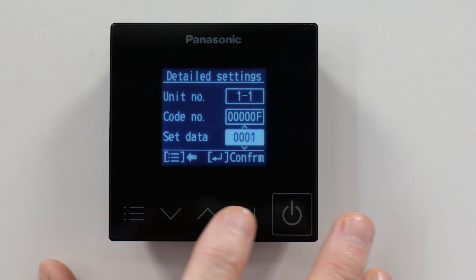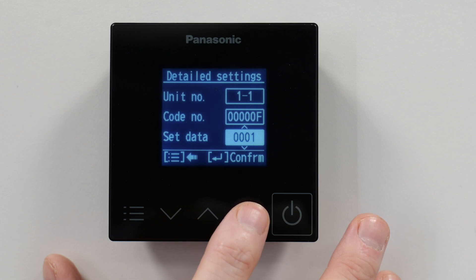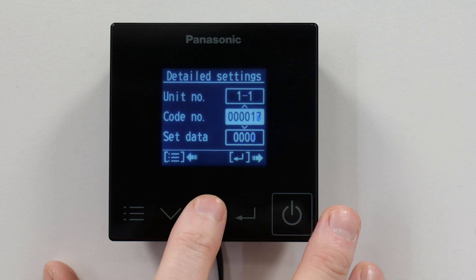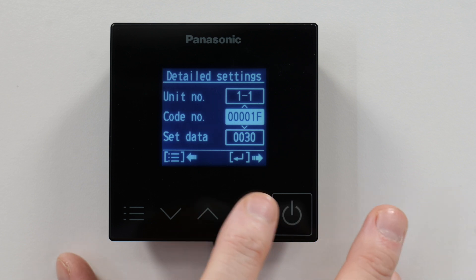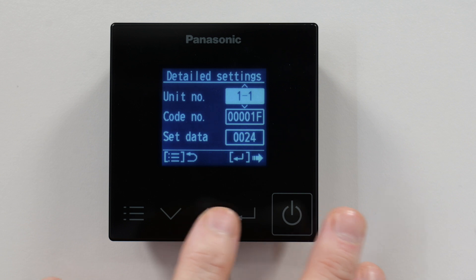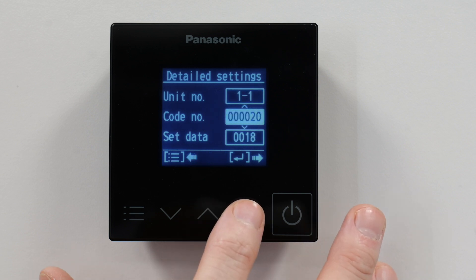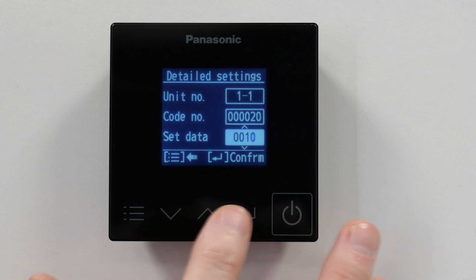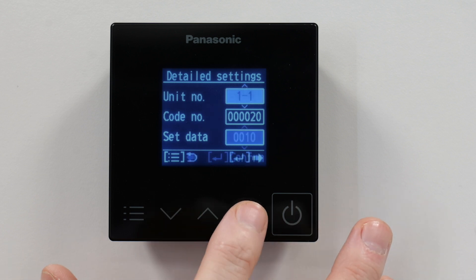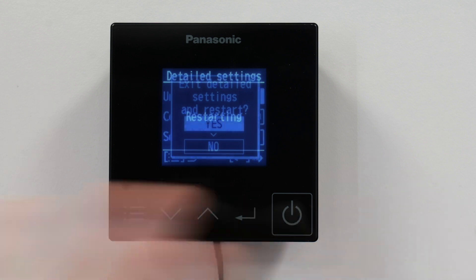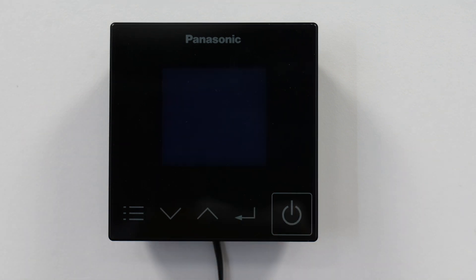We then set code 0F, which is cooling only, to 0001. Then we set the upper and lower limit for cooling. Start with code 1F for the upper limit — set that to 0024. Then the lower limit, which is code 20 — set that to 0010. Once you've done that, press the menu button, exit detail settings, and restart. Your low temperature setup is now complete.